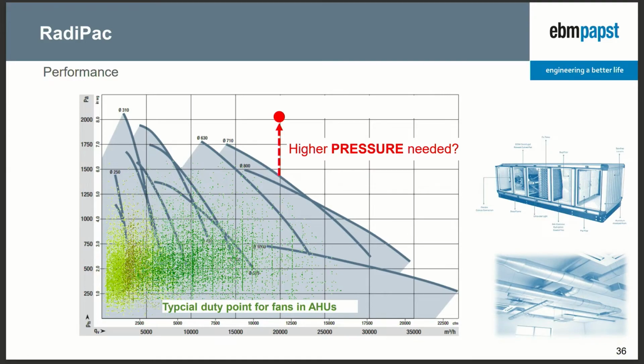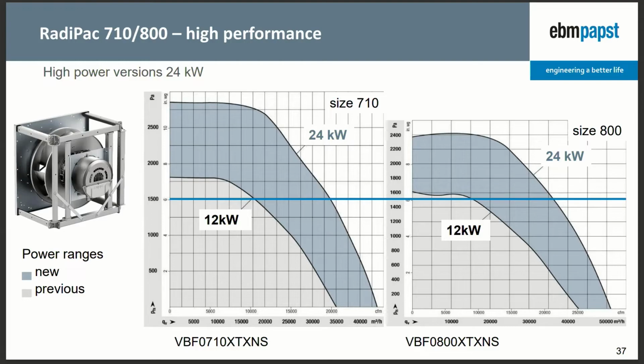So we have a certain performance with our fans, but sometimes we find applications in the market where you need more pressure, for example. So here is the range of the fan, and the dots are, let's say, projects that we got from a customer of ours. So sometimes, as mentioned, you need higher pressure. What can you do? For that reason, we created a more powerful EC motor. This motor is a 24 kilowatt EC motor, meaning 24 kilowatt with integrated electronics.